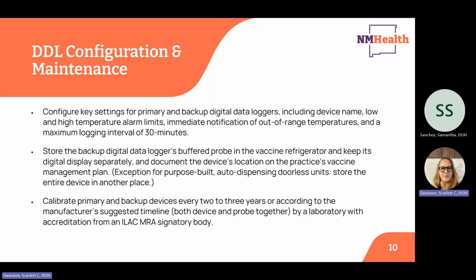As we said, you're required to keep on hand at least one backup battery-operated digital data logger for use during recalibration. If your primary device breaks, if your primary device doesn't meet calibration requirements, or during emergency vaccine transport. Certificates issued by non-accredited laboratories must meet all VFC program requirements for certificates of calibration. Calibrate your primary and backup devices on different schedules to ensure that all of your refrigerators and freezers storing VFC supplied vaccines are equipped with data loggers at all times.